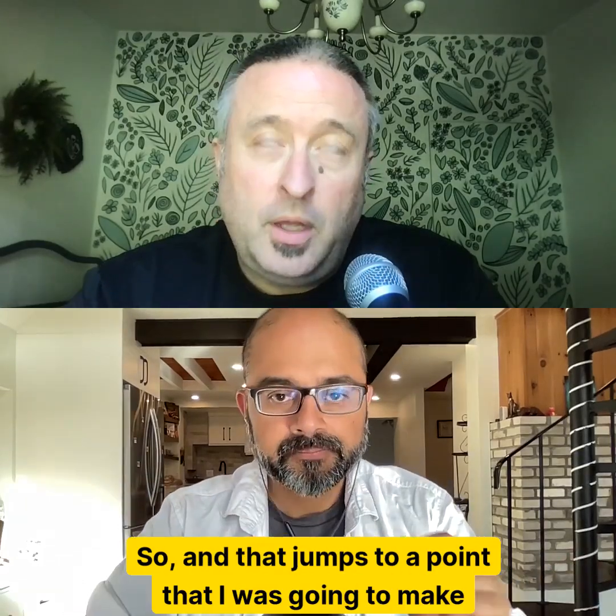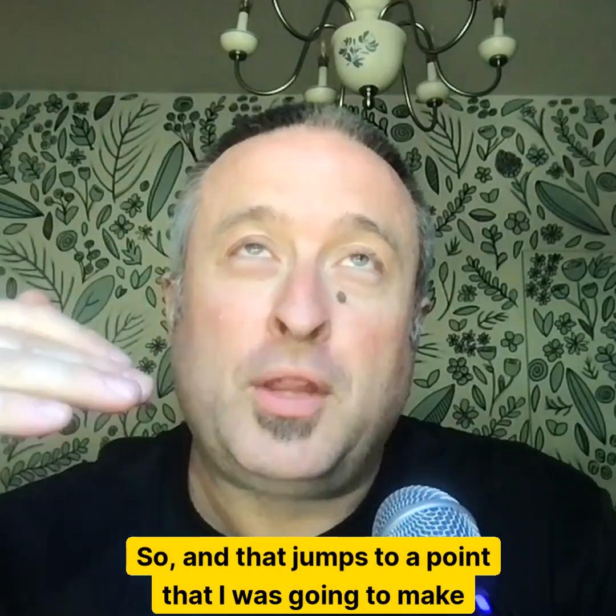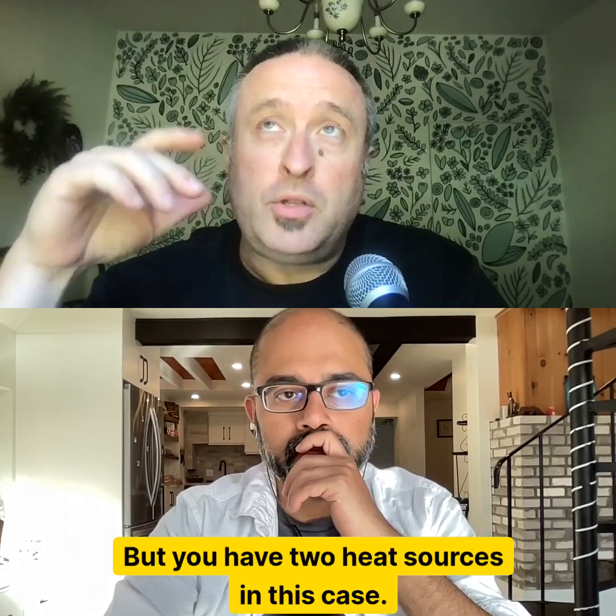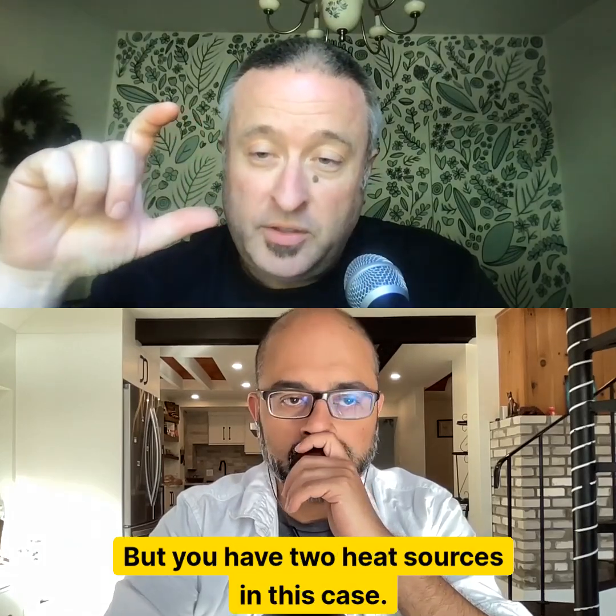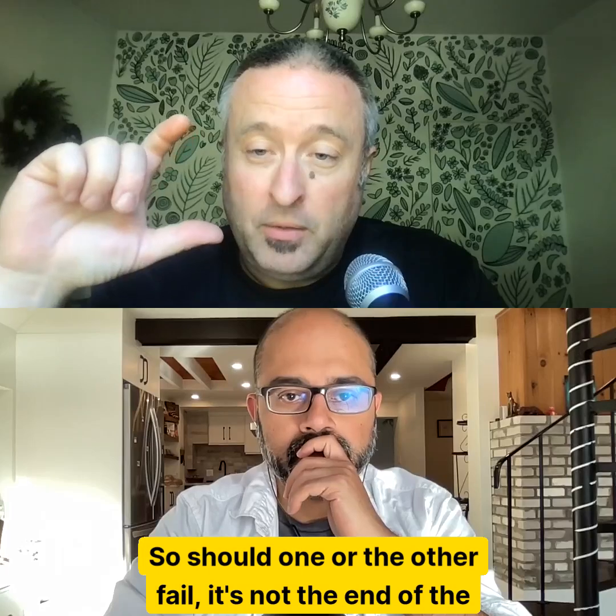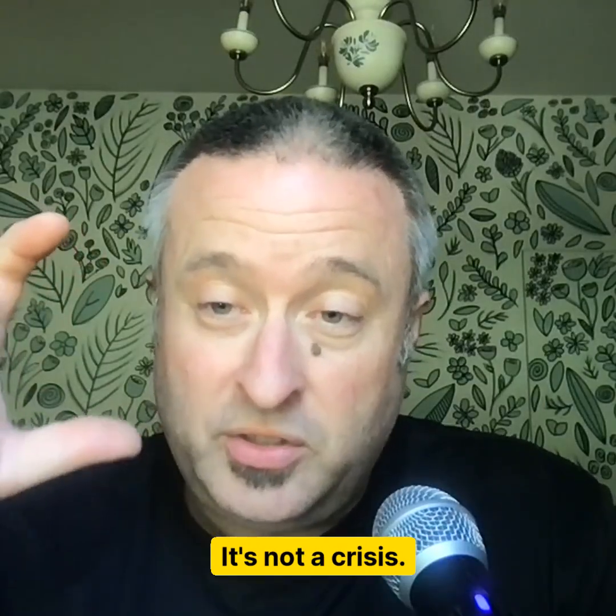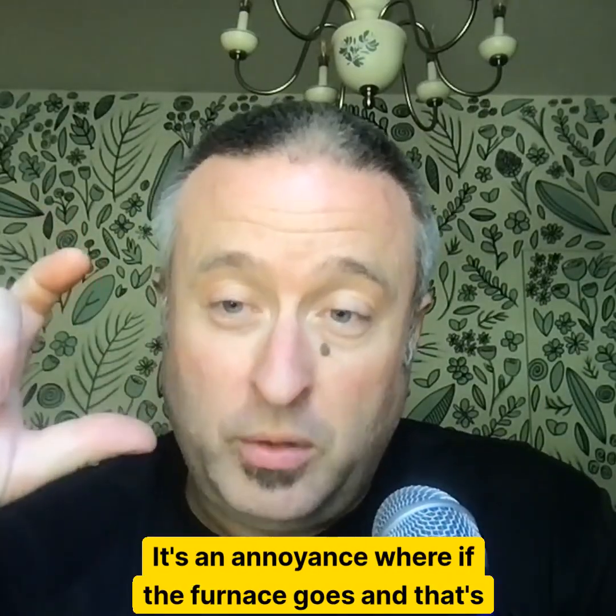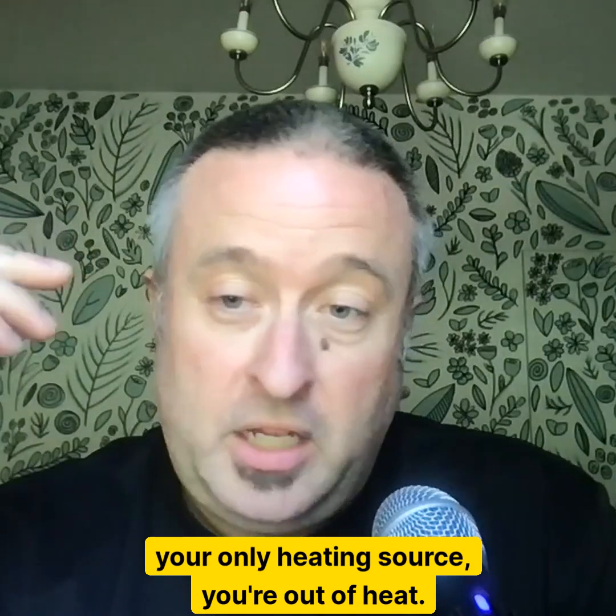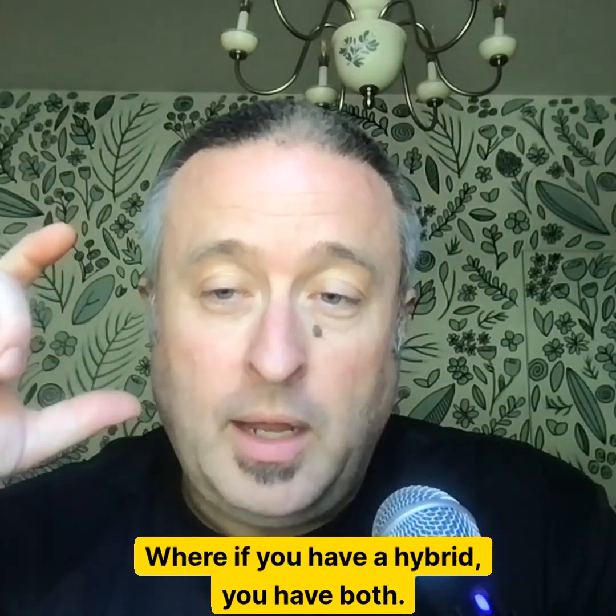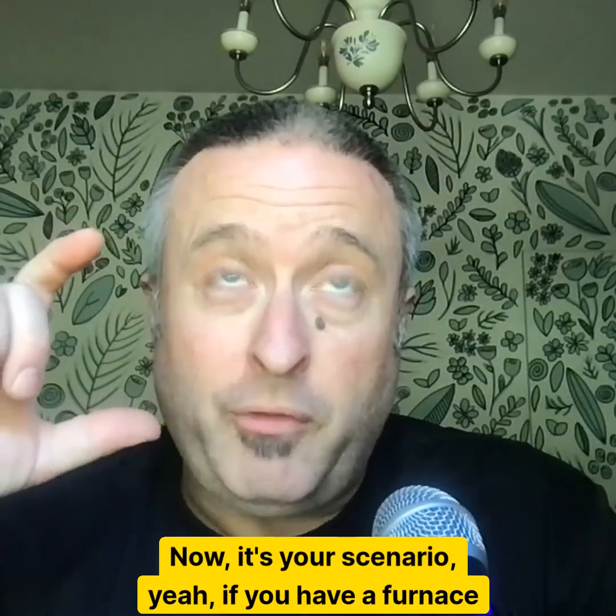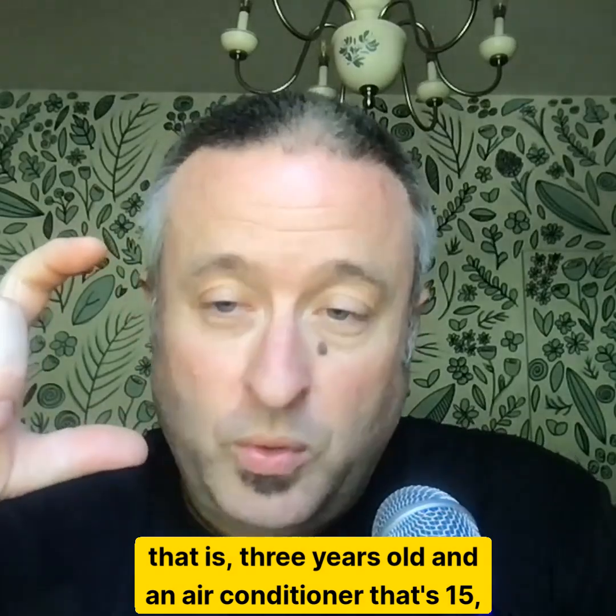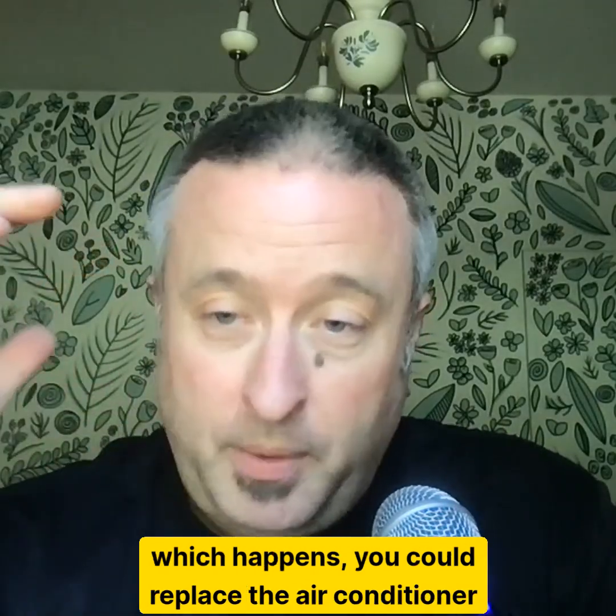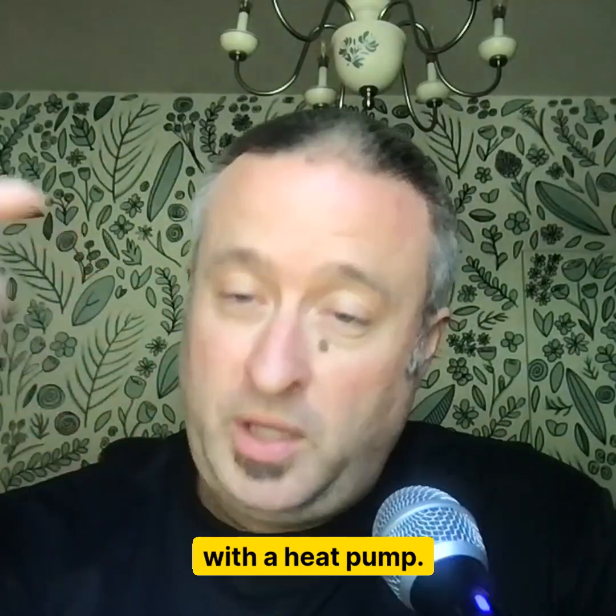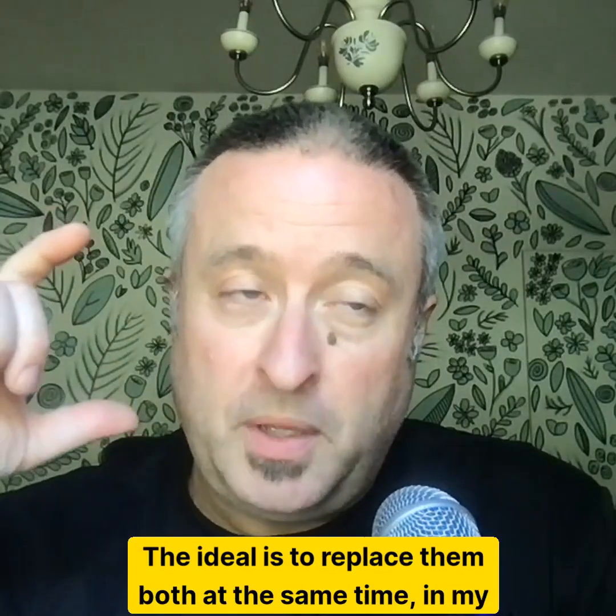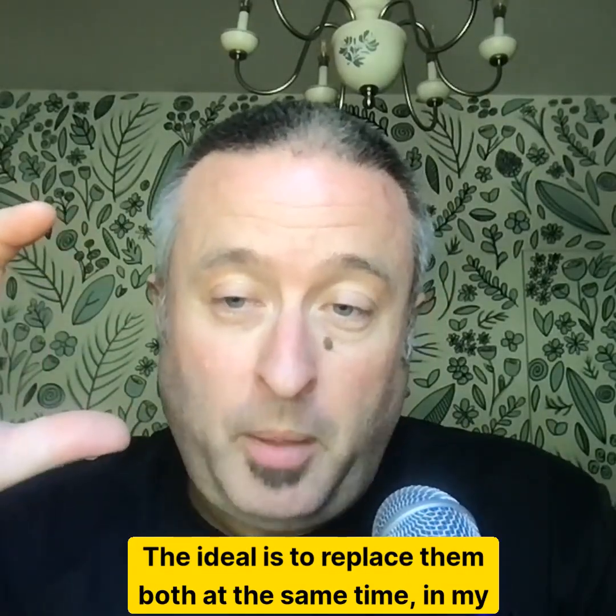Yeah. And that jumps to a point that I was going to make later, but you have two heat sources in this case. So should one or the other fail, it's not the end of the world. It's not a crisis. It's an annoyance. Where if the furnace goes and that's your only heating source, you're out of heat. Where if you have a hybrid, you have both. Now, to your scenario, if you have a furnace that is, say, 3 years old and an air conditioner that's 15, which happens, you could replace the air conditioner with a heat pump. The ideal is to replace them both at the same time, in my mind, both sides.